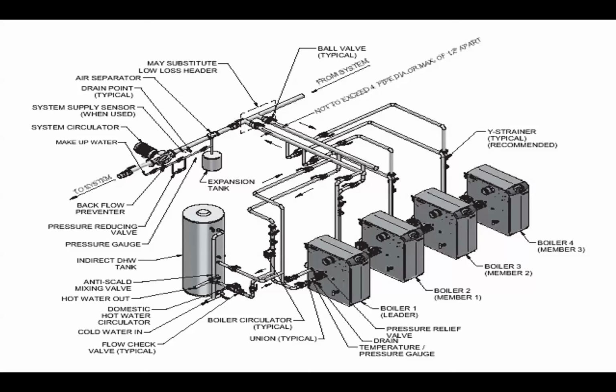So it's a simple little drawing, but it hits on a lot of different points that we need to cover if you're sitting down, and maybe you've already done some of this and you're just reconfirming some of the principles, or maybe it's somewhat new, and we'll touch on it. Fill valves, a pressure reducing valve that's going to bring city water, say, in and fill that hydronic system, make sure it's completely filled with water. What is it? How do we set it? Why is it needed? How does it work hand in hand with its setting, with the pre-charge that's going to take place in that bladder or diaphragm expansion tank you're going to specify, or size and specify? So all these little nuances all work together. It's a simple little drawing, but we touch this every day, somewhere along the way.